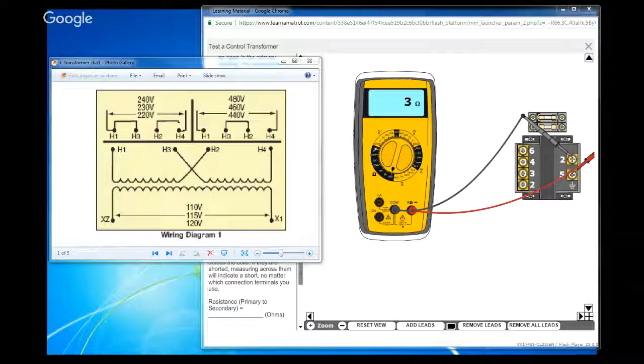So they add taps that we can configure our control transformer to drop, say, 480 down to 120 volts AC, or we can configure it to drop 220 volts down to 110 volts AC. So pretty much all of them will have a diagram on the front of them, okay? Now, if we have problems with our transformer, as in blowing fuses, it may not be a load problem. We could have a bad transformer. They do go bad.